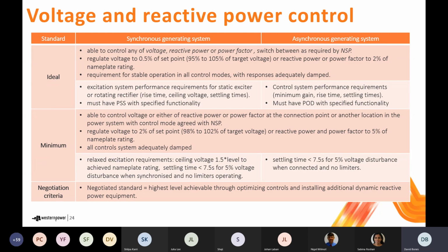The minimum standard is expressed in a similar way, but the requirements are relaxed in a particular fashion. So instead of the requirement to be able to regulate voltage, reactive power and power factor, with the choice as to which mode you're in being made by the NSP, when you're operating to the minimum standard, you're able to choose one of those quantities to control. When you're regulating one of those quantities, you still have to be able to operate stably and have a stable control system. The regulation range and the performance is reduced a bit compared to the ideal standard. So you're required to achieve 2% of the set point for voltage control and 5% of nameplate rating for power factor or reactive power.